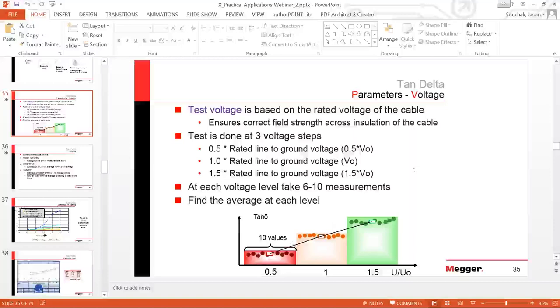How do the operating temperature and loading variation influence the degradation of cable insulation? Okay, it's basically coming down to the temperature or loading. Typically, loading equates to temperature, because if I have more load on it, I have more resistance, so I get a higher temperature. And the aging of cables, these aging processes that we have in the cable, are basically chemical reactions that change the polymeric material, or that change the paper when I have paper oil insulated cables.